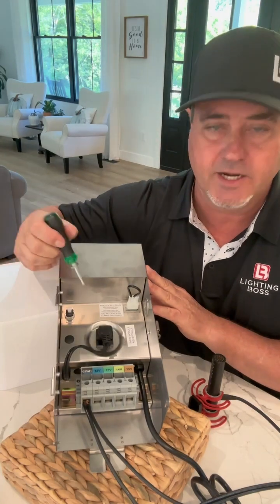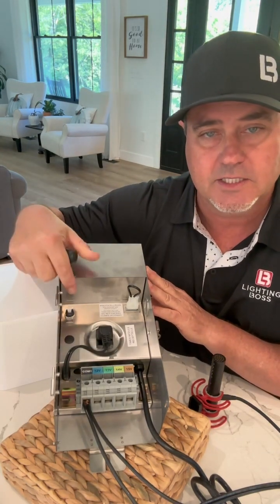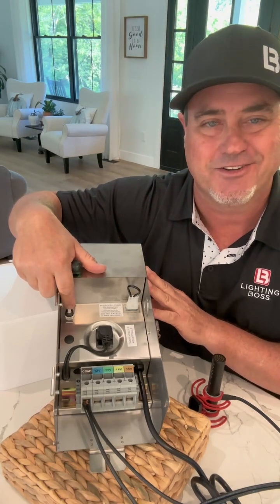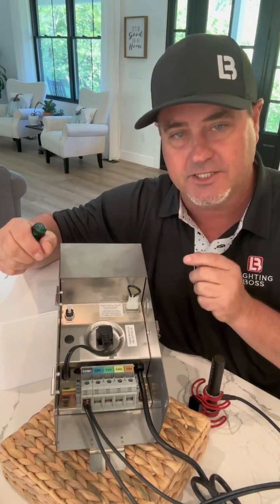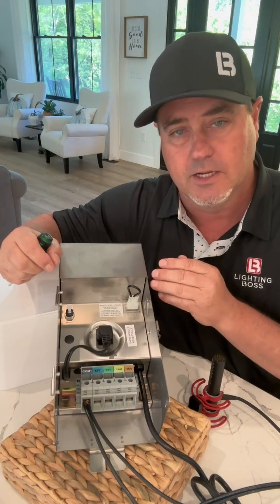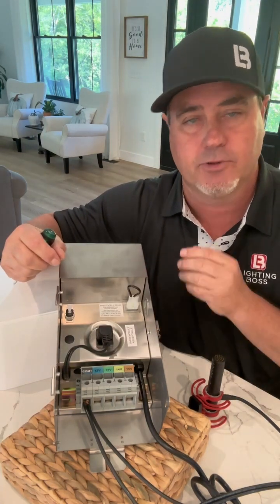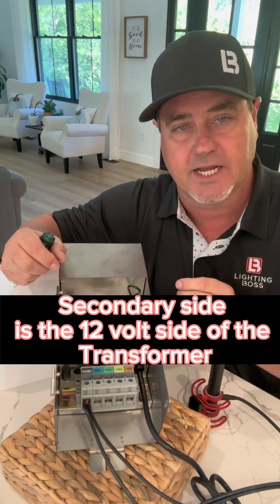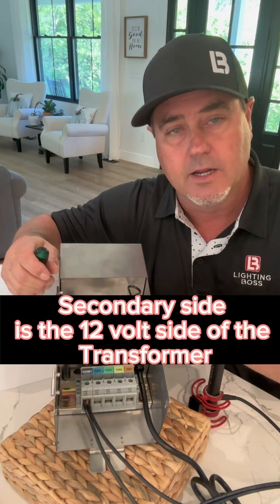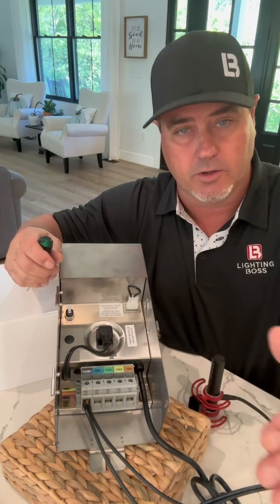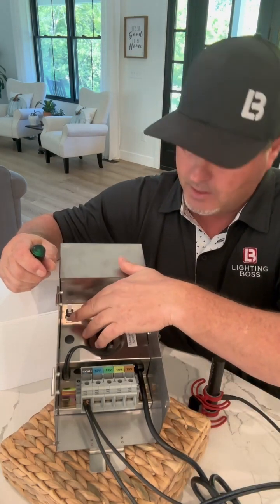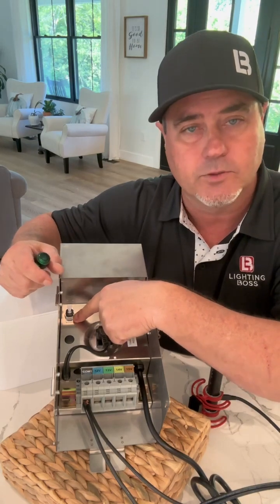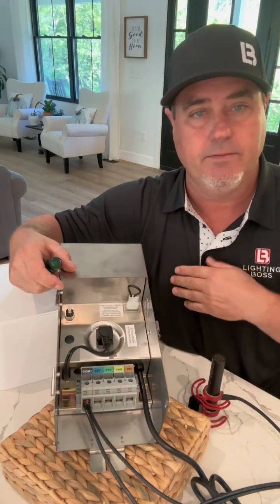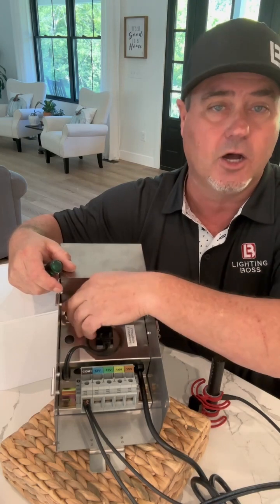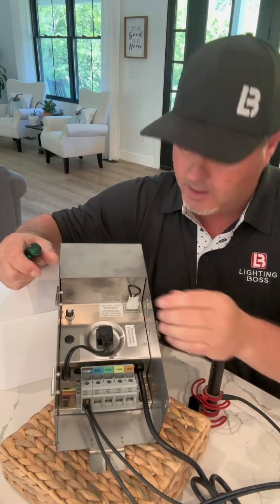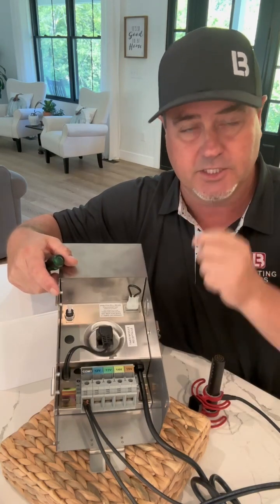Another thing that you're going to notice in here is a little white toggle switch. This toggle switch is not just a little switch to turn your transformer on and off. It's actually a fuse behind here that is protecting the secondary side of the transformer. So everything from the transformer out to all your lights, it's controlling that. There's an on and off switch, and when it's on, obviously your lights are going to work. If it's ever kicked off, the lights will not come on at all. The toggle switch needs to be in the up position to operate.